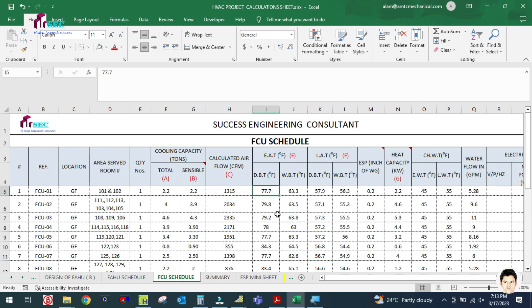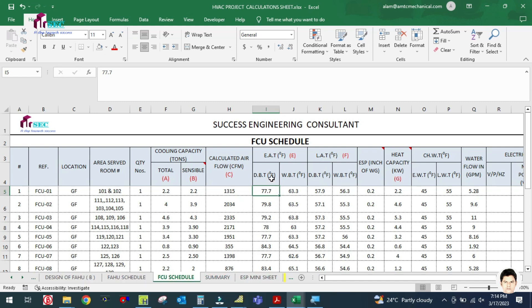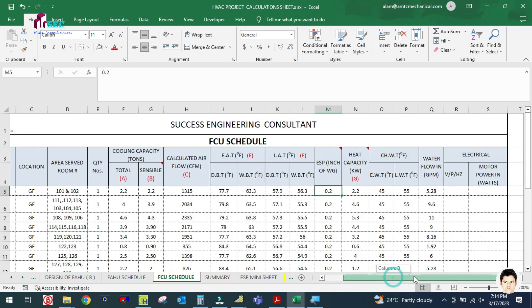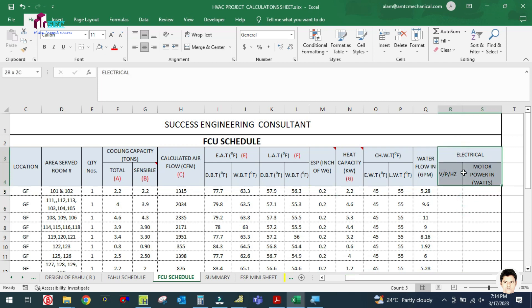You also enter the calculated fresh air, the on-coil temperature (EAT — entering air temperature) with dry bulb and wet bulb values, and the off-coil temperature (LAT — leaving air temperature) with dry bulb and wet bulb values. Additional fields include ESP, heating capacity, chilled water supply and return temperatures, water flow rate in GPM, and electrical data — voltage, phase, and motor wattage.